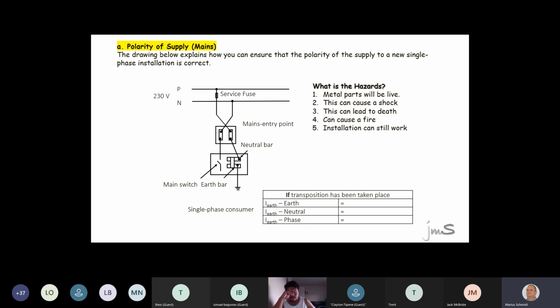Yep. Can an appliance still work if you swap phase and neutral around? I would say yes. Can your kettle work if you swap phase and neutral around? Yes. What conductor do we switch? We switch the neutral. Now, what's very, very important? Can you see on my picture there's a service fuse, the fuse in the plinth? Will the fuse blow or not?